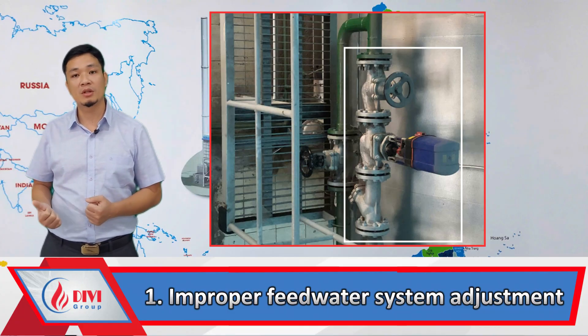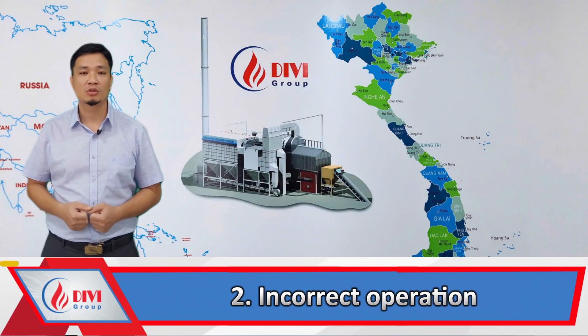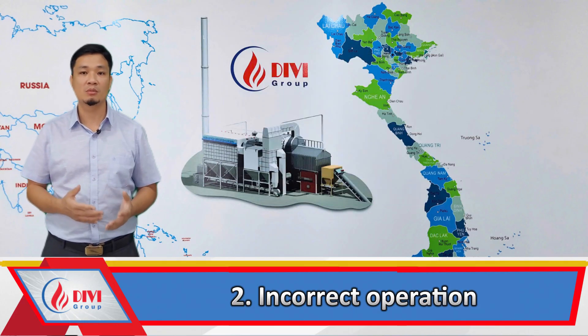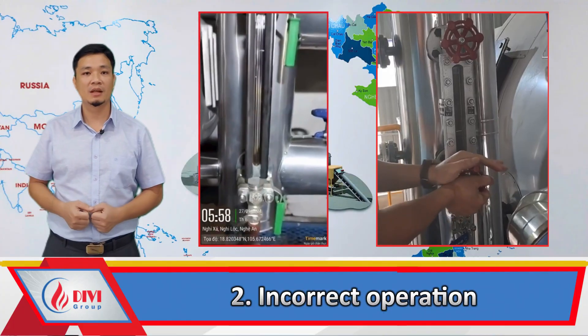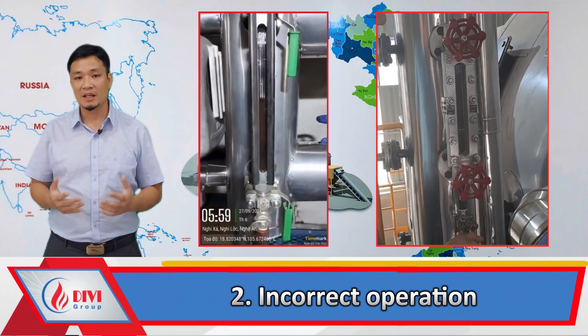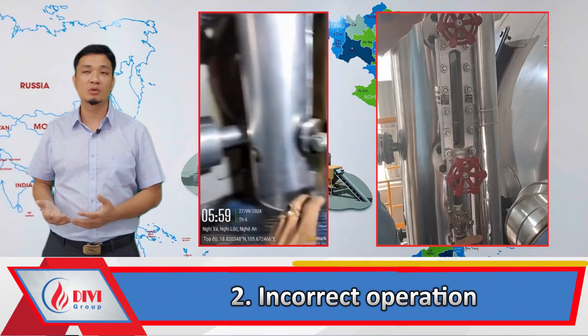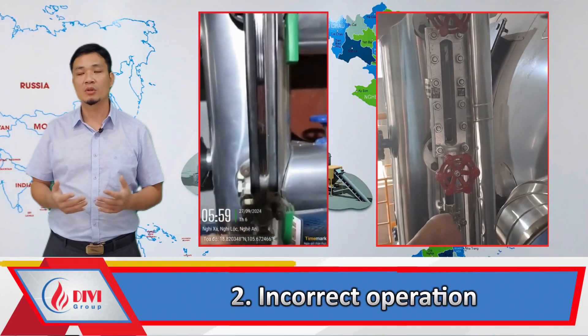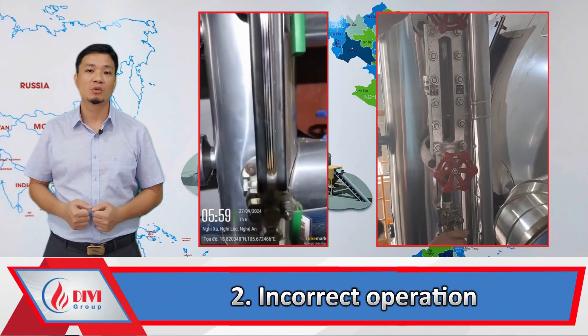Cause 1.2: incorrect operation. The operator fails to thoroughly check the water level before starting the boiler, leading to excessive water supply. As the water heats up, it expands in volume and overflows. The operator may also neglect to monitor the sight glass or the signals from the water level system during operation.